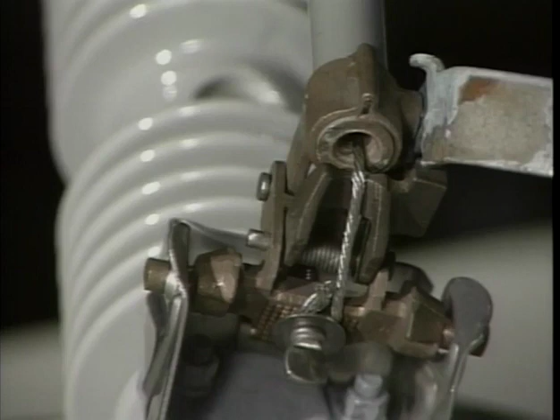A load break disconnect switch can operate under load to de-energize and isolate a circuit. Like the other type of switch, its parts include a disconnect assembly, a switching arm, switching contacts here and here, and a latch. Note that the switching arm in this case is not one solid piece. It contains a cylindrical housing or fuse tube. And inside the fuse tube is a fuse link. At the hinge in the switching arm, the fuse link is connected to a latch.